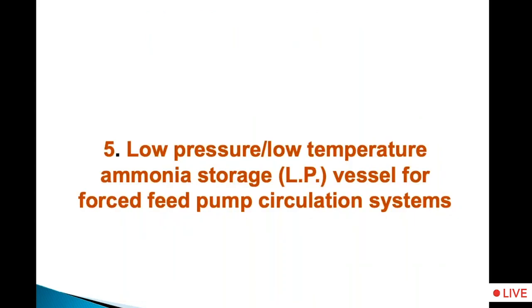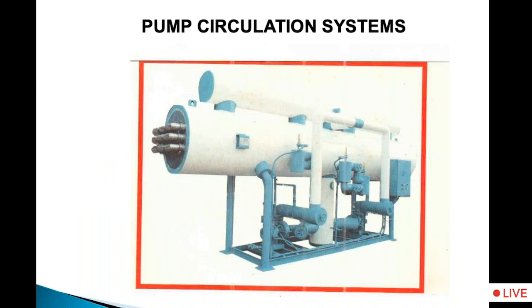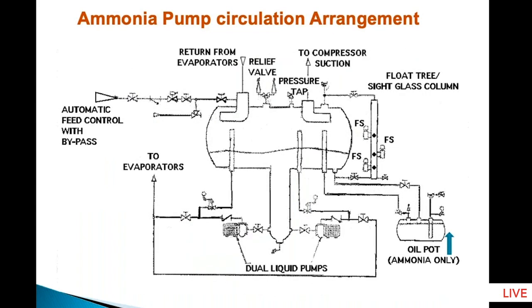Now we go to the most important vessel, the low pressure, low temperature ammonia vessel. A full session can be conducted only on the design of this LP vessel, but we will take some important points of the LP vessel. This is an LP vessel, an ammonia pump circulation vessel. There are two pumps, if you see, one pump working, one pump standby, and this LP vessel is a low pressure vessel.